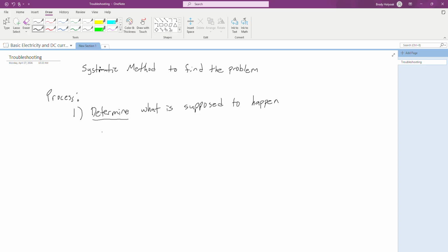Once we've identified a problem, we correct it. We swap a part out. We move a component. We isolate what is going on until we can get to the point where it works correctly. Then we correct it, we verify it's running, and we put it back in there. All of our measurements should be back within our margin of error that is predetermined, and in our program, it's going to be 5%.